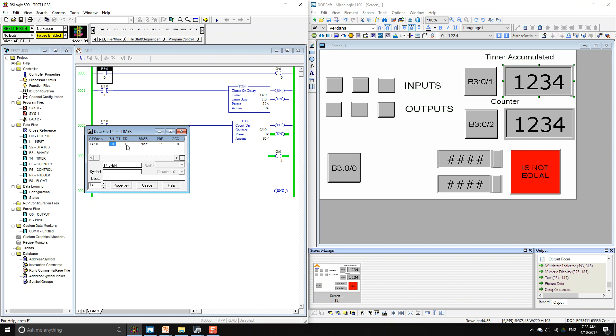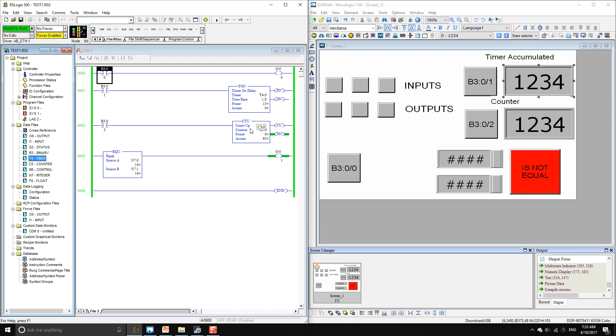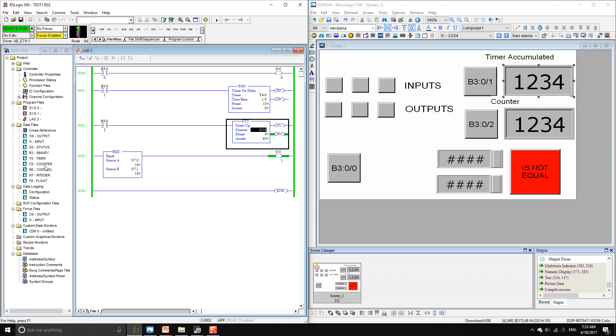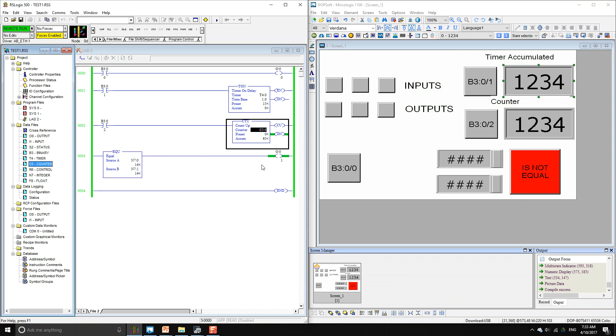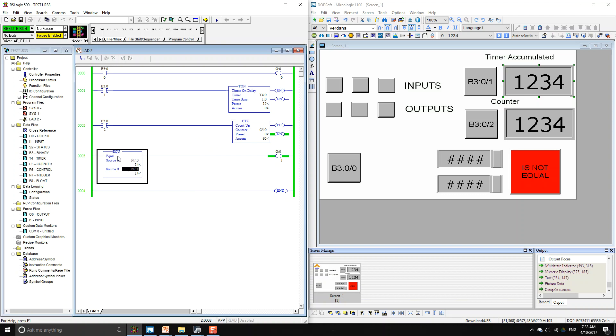the done bit is going to get activated. To access that bit you use T4:0/DN. You can get it right there. The same approach applies to counters — if you go to Counters, we're only using counter zero and we're going to reference its accumulated value. We're also using a function to see if two integers are equal.